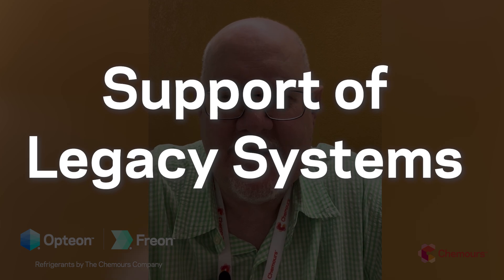Starting with those legacy systems — those systems are going to continue to age, and a certain percentage every year will reach their useful end of life. Being prepared to have those discussions with your customers about the best path forward as things age out is important. If systems still have good usable life, you may consider a retrofit. We've done tons of retrofits — things like R22 to MO99 on the air conditioning side, and 449A or 448 on the commercial refrigeration side. There are a lot of possibilities for equipment that still has existing life, depending on the age, condition, overall fleet size, budgets, timeframes, and sustainability goals of that customer.